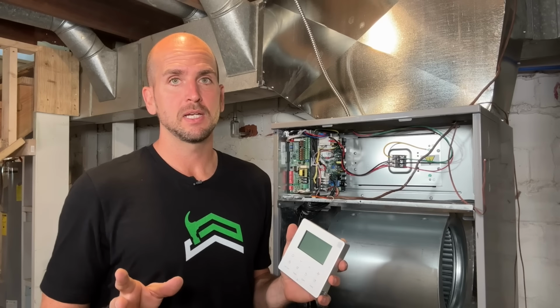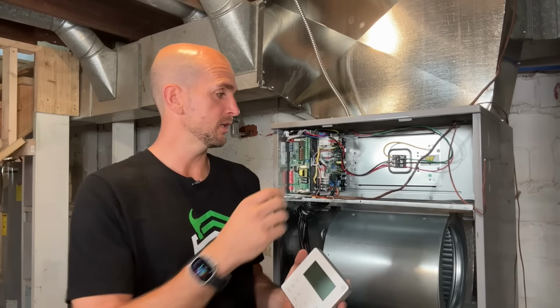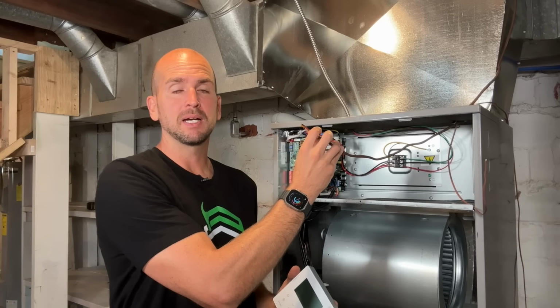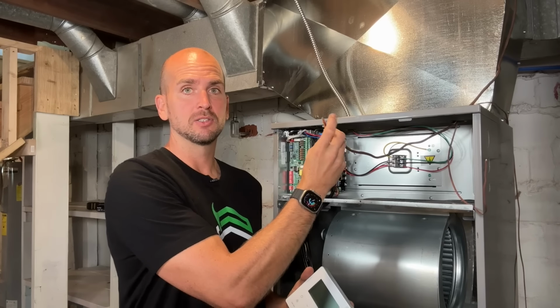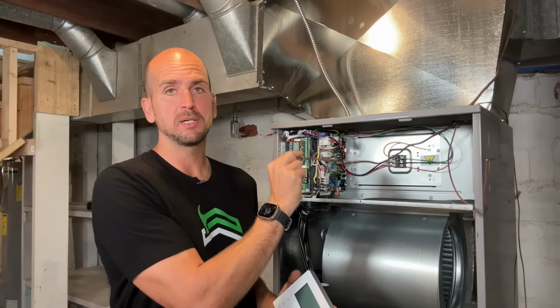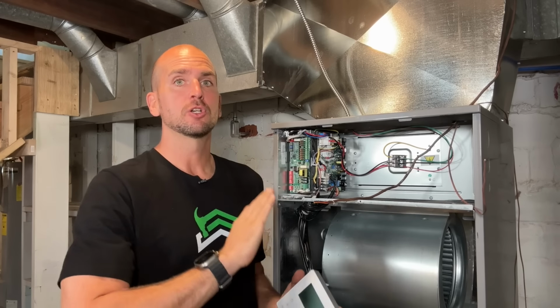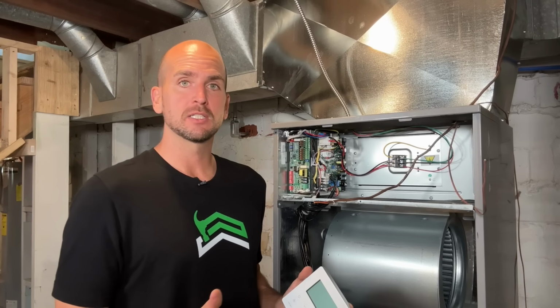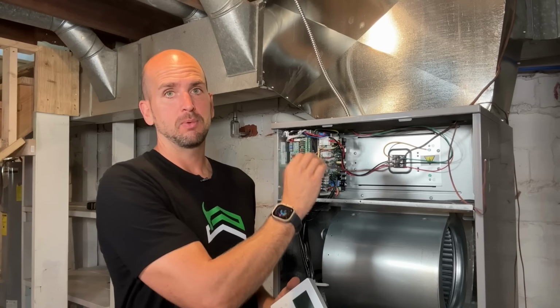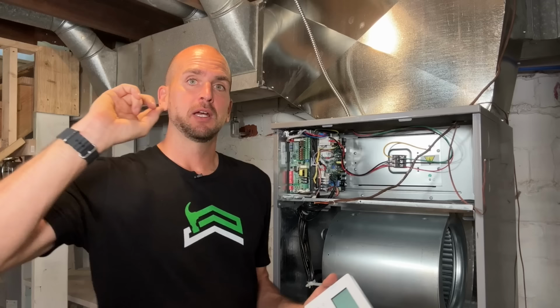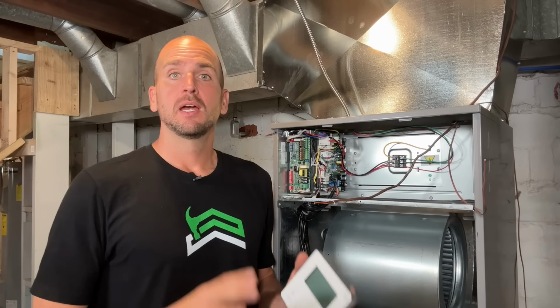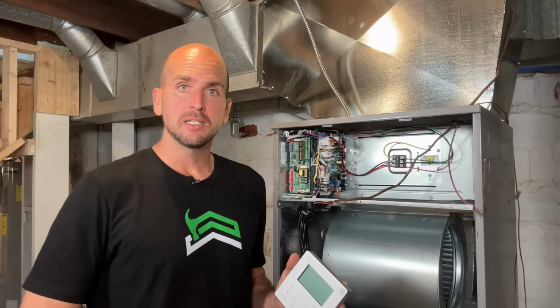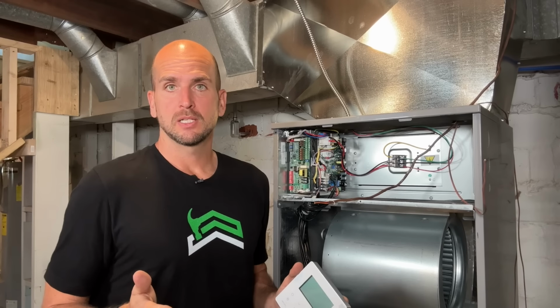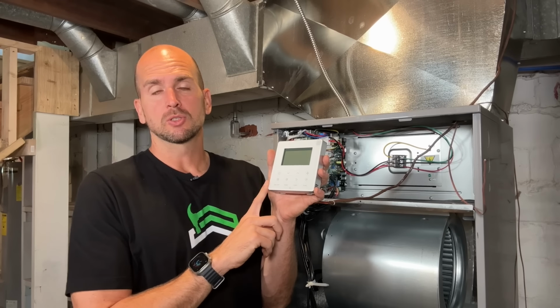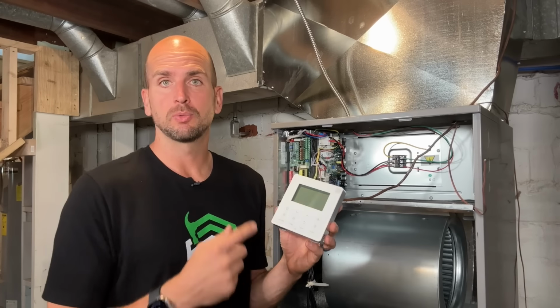Unlike normal thermostats, which might have many different wires, I am keeping my 18 gauge 7, so it actually has 8 different wires in this bundle. I'm keeping that in place. So in the future, if I want to switch to a Nest thermostat, this thermostat wire that runs between the air handler and then up to the living space is going to be the thermostat wire I need to accommodate a Nest thermostat. Why I'm going to use this Mr. Cool unit, because I just personally want to try it out.